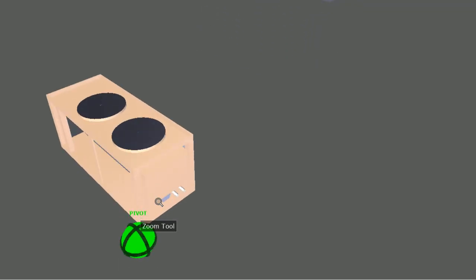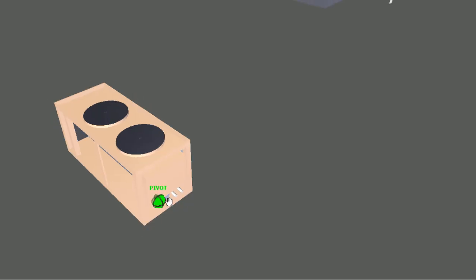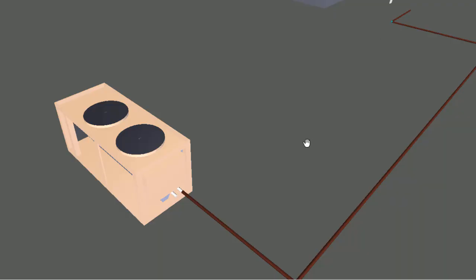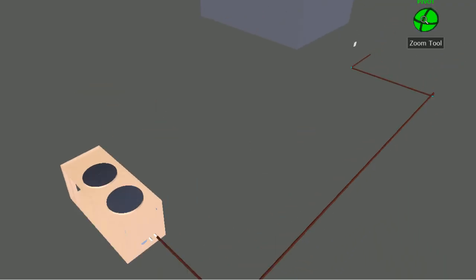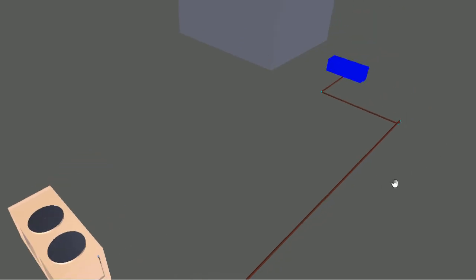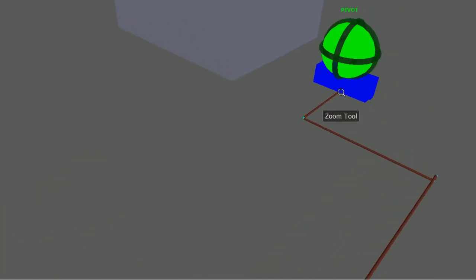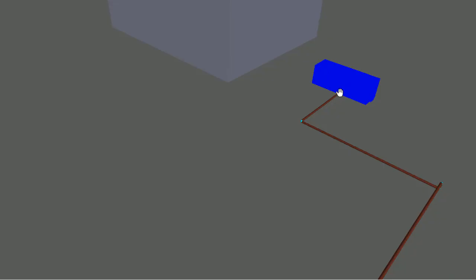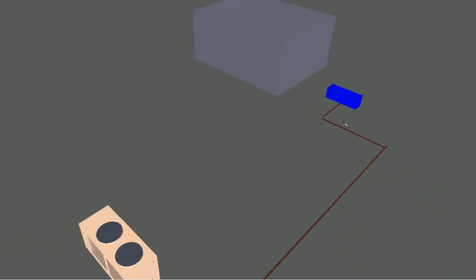You see this is the air-cooled chiller. Now we can make a connection from this evaporator of the chiller to the AHU. Here you see a pipe; with the help of this pipe, the water goes through and enters the cooling coil of the air handling unit. This is chilled water because, as we discussed earlier, in the evaporator the refrigerant takes heat from the water. So this chilled water goes from the air-cooled chiller to the air handling unit.